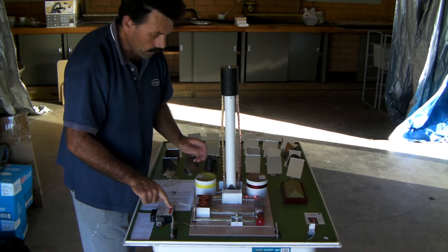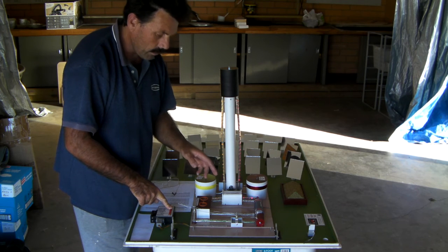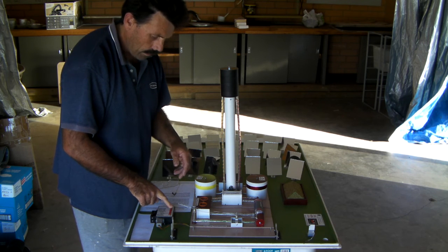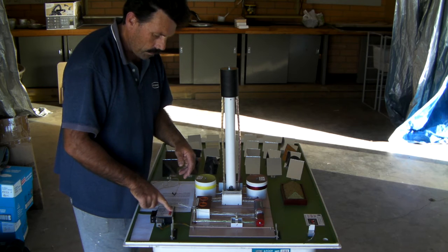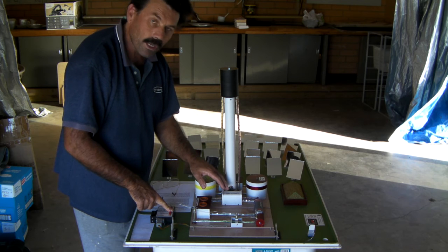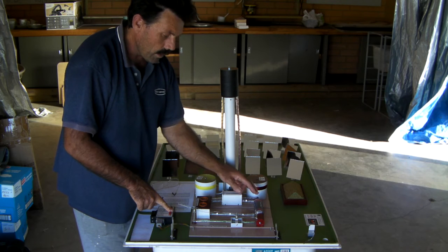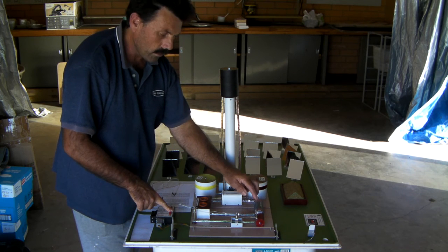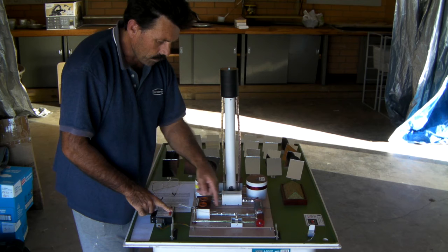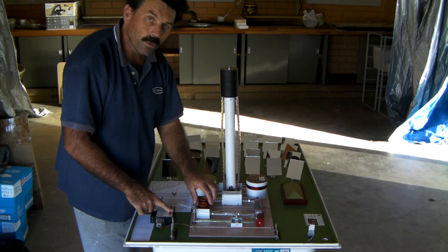And that works like this — it's just a closed loop system. It goes around and around through the heat exchanger, up to the water which turns it into steam. So that's the other cycle here: the steam cycle. It comes out of the condenser as water, goes into the heat exchanger, the hot salt flashes it off into superheated steam, which then goes to the turbine and drives the turbine, which generates the power going out to the grid. So that's a closed loop system as well — the water just continually goes around and around through this air-cooled condenser.